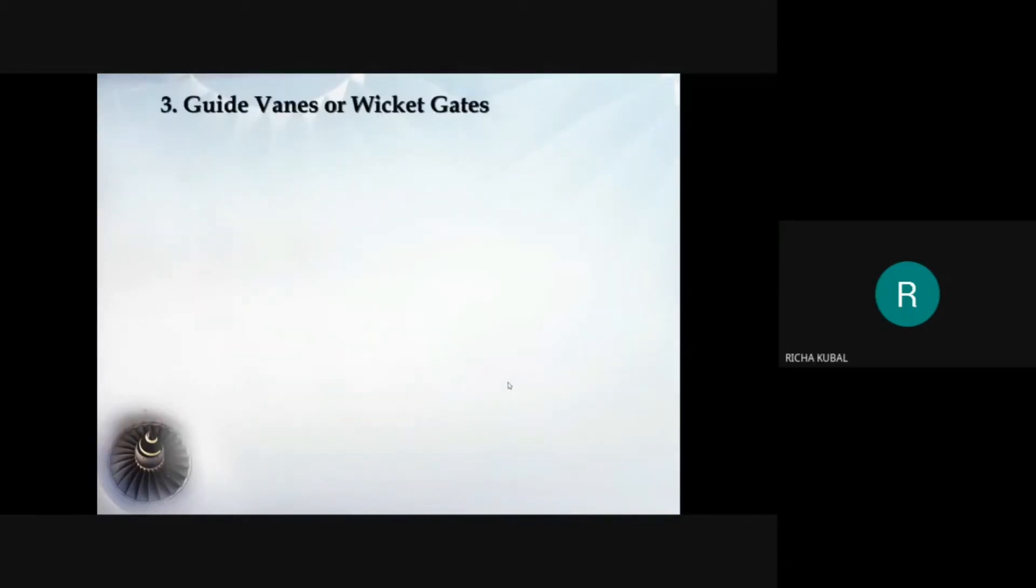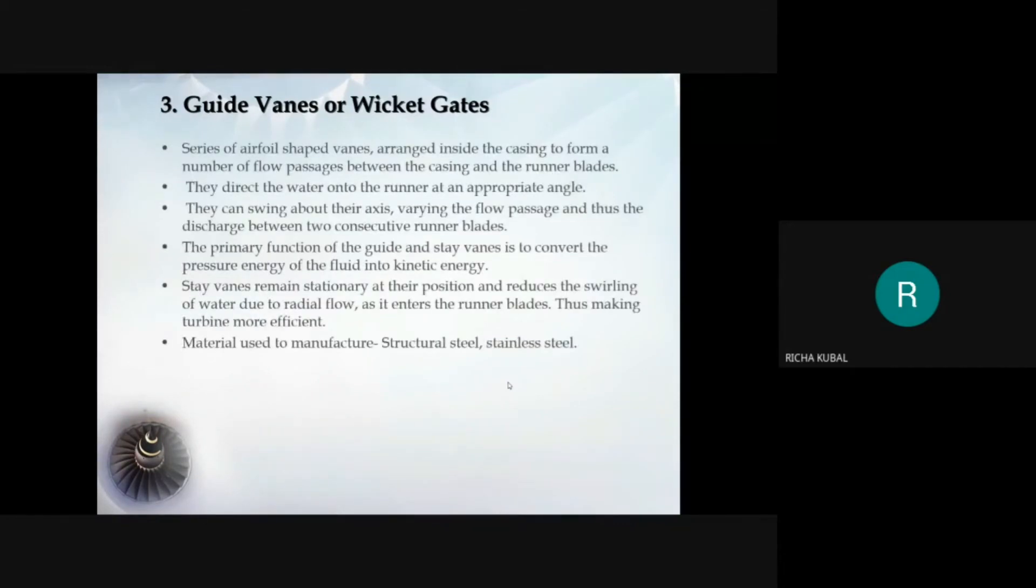Third important component is the guide mechanism. It consists of stationary ring in a form of wheel called as guide wheel. It surrounds the outer periphery of runner and is fixed to inner surface of casing. In between the outer and inner ring of guide wheel, there is a series of guide vanes or also known as wicket gates of aerofoil section present. This gate forms number of passages between casing and runner blades.